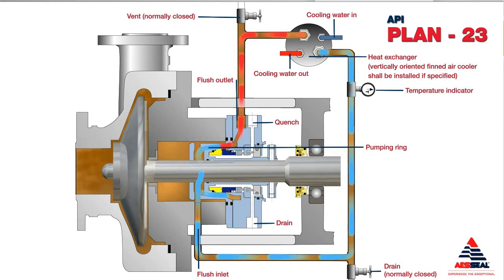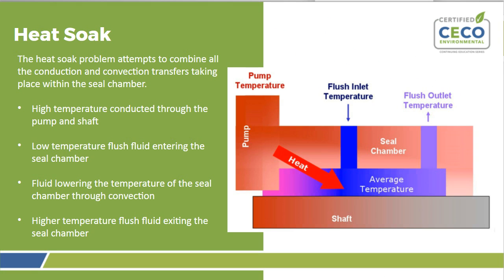The Plan 23 method is by far the preferred method in most cases because it's much more efficient. You use less cooling water, and you lose less BTUs out of your system to cooling the seal. This is basically done through a phenomenon called a heat soak. The high temperature conducted through the pump and shaft.